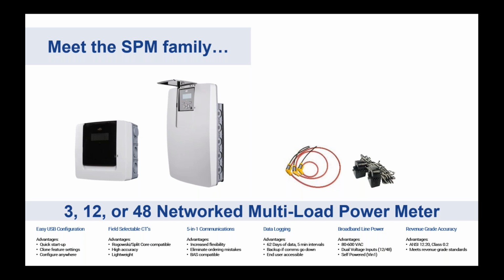Each one of those voltage inputs operates from 80 to 600 volts, plus or minus 10%, giving you a wide range. So again, you don't have to buy a meter rated for 277 volts or 480 volts. You can meet those demands all through configuration of software, and the meter will handle that wide range of voltage. The meter is also ANSI C12.20 class 0.2. So very accurate meter and will meet most of the accuracy demands out there in the field.